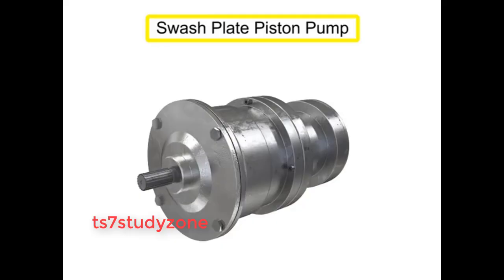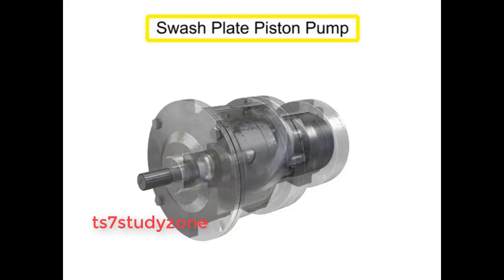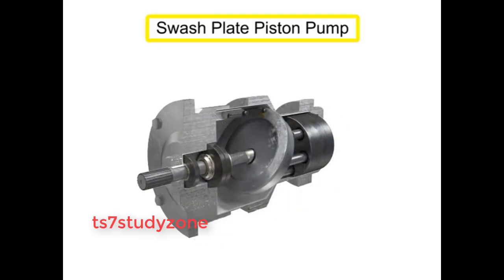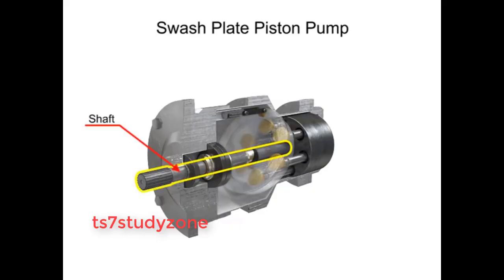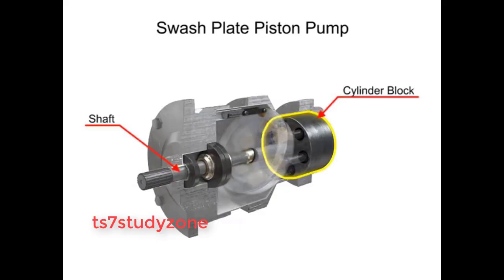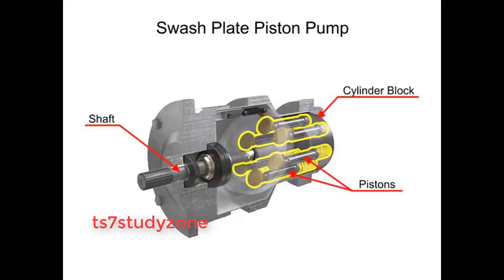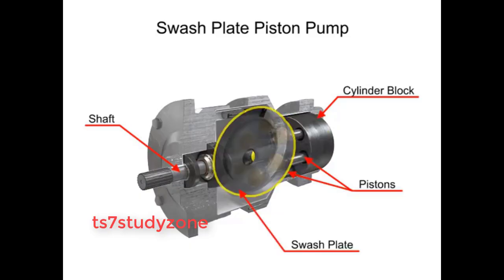A swashplate is a device used to translate the motion of a rotating shaft into the reciprocating motion of a piston. Swashplate piston pumps have a rotating shaft connected to a cylinder block containing pistons, which are pressed against a stationary swashplate that sits at an angle to the cylinder.